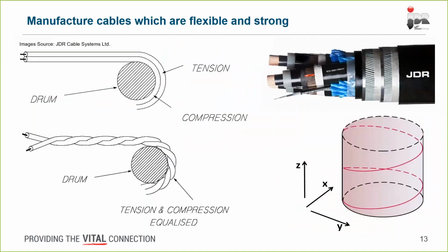In terms of how we build the cables, we twist up our conductors, applying the twist so they form a helical structure within the bundle. We do that to equalize the tension and compression seen when we bend the cable in its entirety. If we bend it around a large OD, one section would see a lot of compression, and another a lot of tension. We try to equalize that so the tension and compression is balanced, which means we can bend the cable to a much smaller diameter without issues.